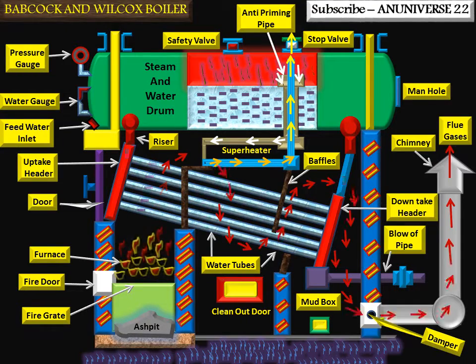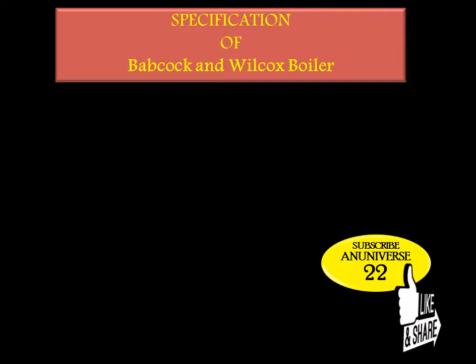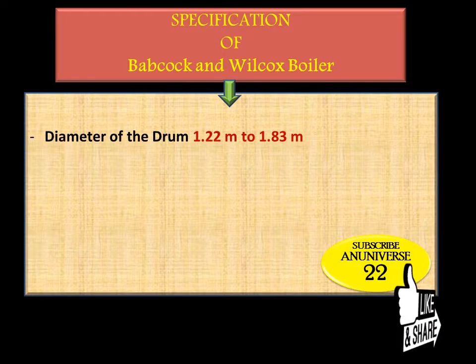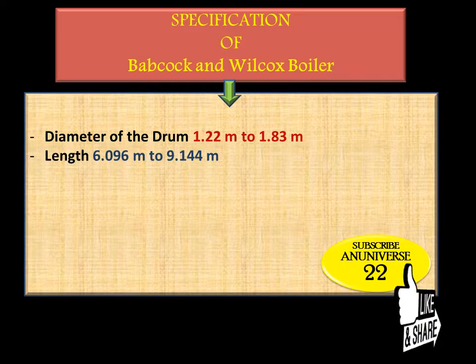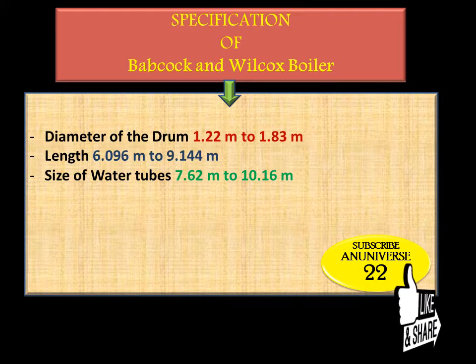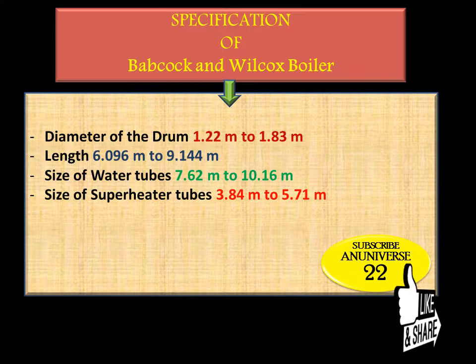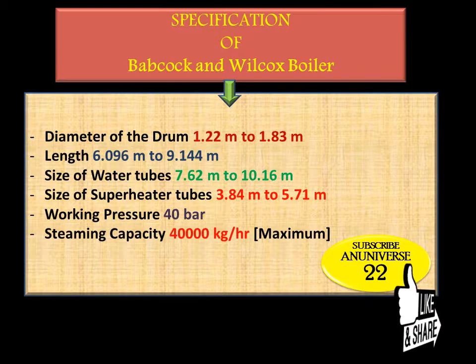The main specifications of the Babcock and Wilcox boiler are: the diameter of the drum generally varies from 1.22 meters to 1.83 meters; length varies from 6.096 to 9.144 meters; size of water tubes 7.62 to 10.16 meters; size of superheater tubes 3.84 to 5.71 meters; working pressure approximately 40 bar; steaming capacity up to 40,000 kg per hour maximum; and efficiency varies from 60 to 80 percent.